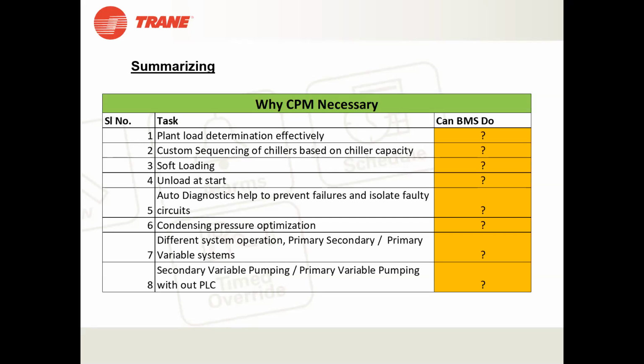VFD chillers may be more efficient at 60% of the load, while non-VFD chillers are efficient at 100% of the load. So we have a feature where we can lock the VFD chillers to run only at 60% of the load unless there is a complete peak demand on the system. This kind of feature can easily be done with Trane chillers using Trane CPM.